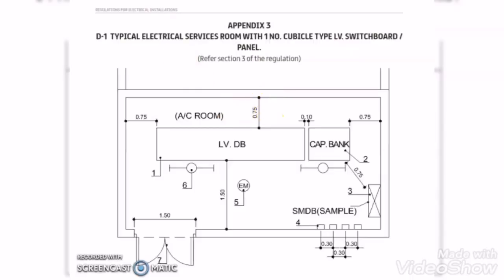As per DEWA regulation, when we are placing any LV panel, the distance between the LV panel back wall and the LV room wall should be minimum 0.75 meter. In the same way, the distance between the side wall of the LV room and the side wall of the LV panel must be 0.75 meter. If either of these distances is less than the minimum required, DEWA will come and reject it.